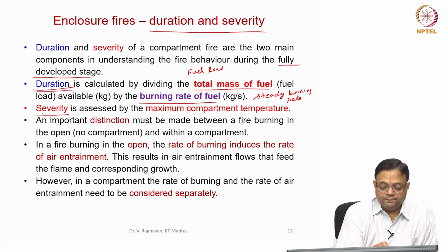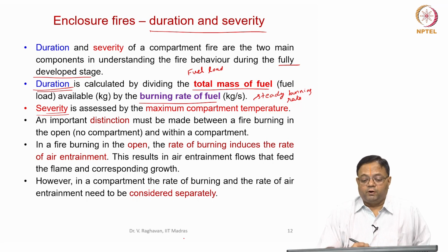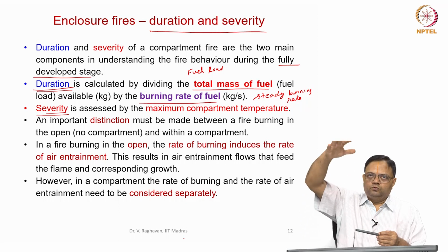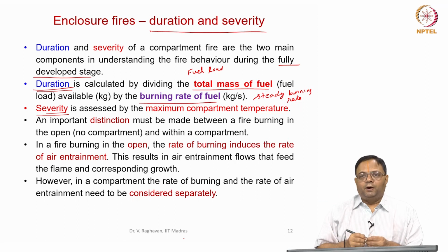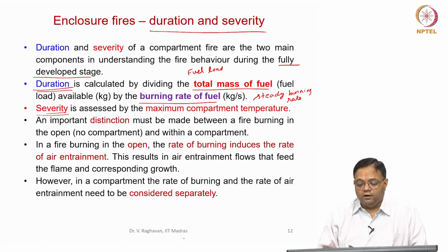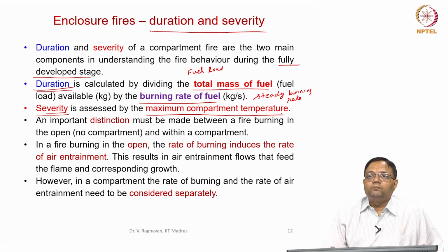Now, severity is quantified by the maximum temperature of the compartment. Some fires can lead to growth of the smoke layer and the smoke layer reaching a temperature of 800 degrees, etc. But in some cases, when energetic materials burn, the temperature can also exceed the value of 800, and may reach 1000, etc.